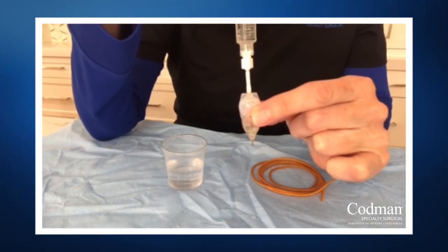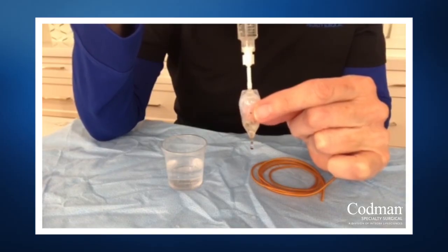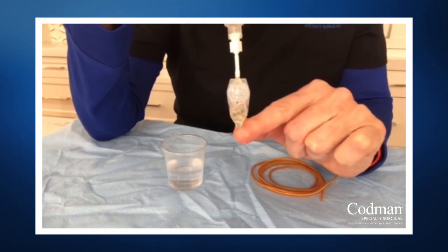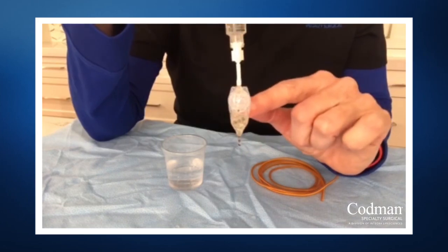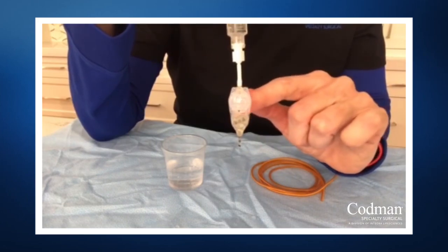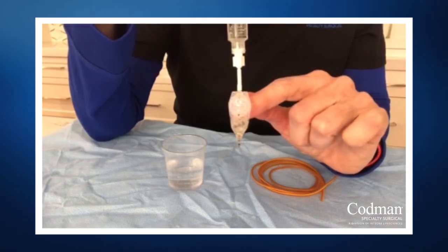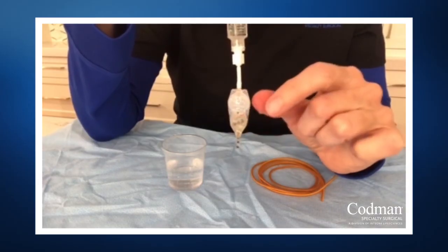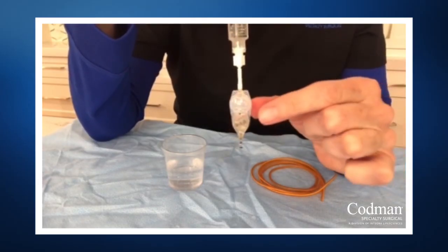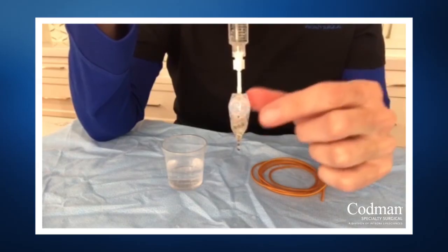So I'm going to push very gently on the syringe, and then you're going to see flow come out of the distal end of the valve. Sometimes in manufacturing, there's a ruby ball and seat that sits just at the inlet portion of the valve from the reservoir, and it becomes stuck. So sometimes you need to push that, and sometimes you'll hear a little pop.